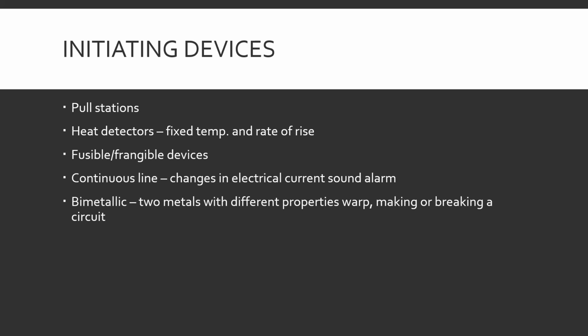Standard stuff. Heat detectors. Fixed temp and rate of rise. That one, again, is pretty easy to decipher. It's a little device on the ceiling, wherever they determine to put one. Well, it kind of has to be up high because heat rises. And all it is is kind of a yes or no thing with fixed temp. If it's set to go off at 180 degrees, for example, and the temperature is 170, it doesn't do anything. If it reaches 180 or goes above that, the detector goes off and it sounds the alarm.